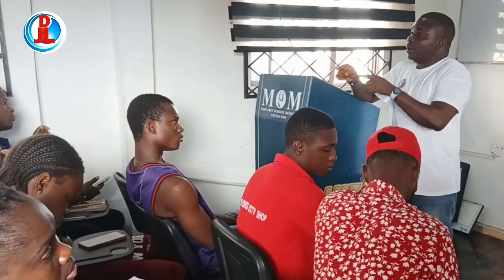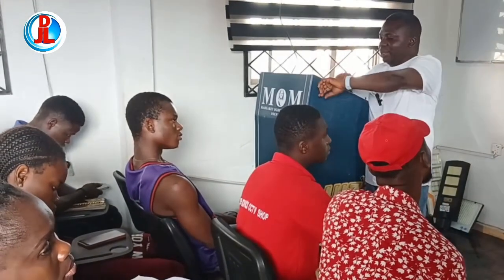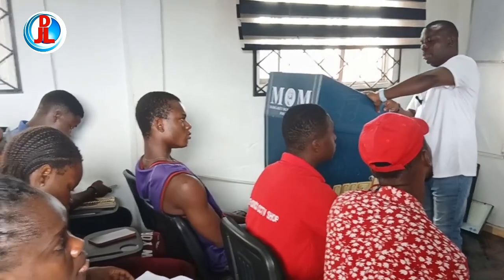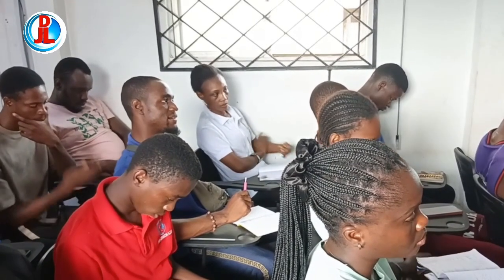Inside that data sheet, you see where they say maximum charging current 60 amps. Go and check, you see it. Maximum charging current 60 amps. Maximum charging current 100 amps, and so on. So set according to the charging current. What did I say? Set according to the charging current. Don't go and set based on what they want. So please, we'll study the data sheet.